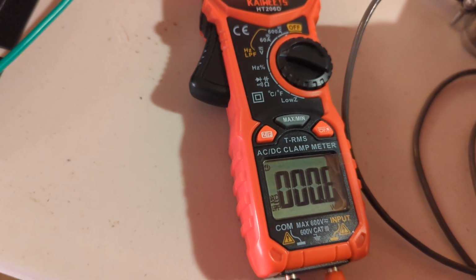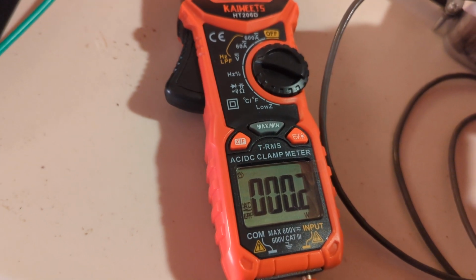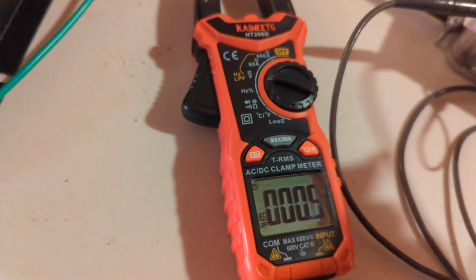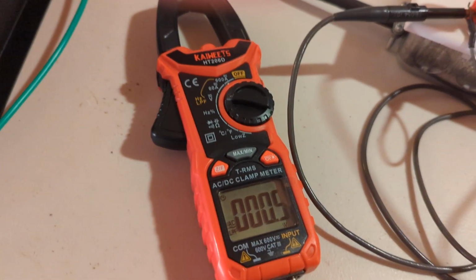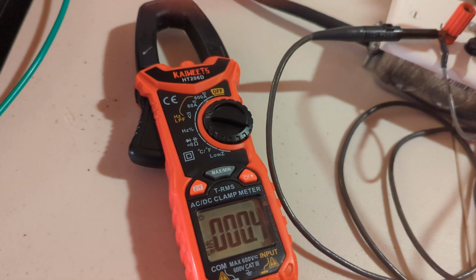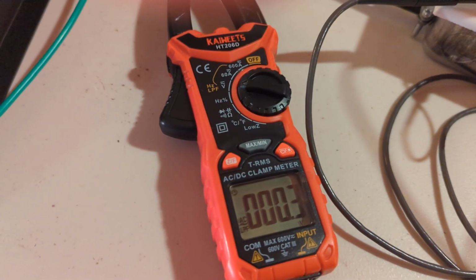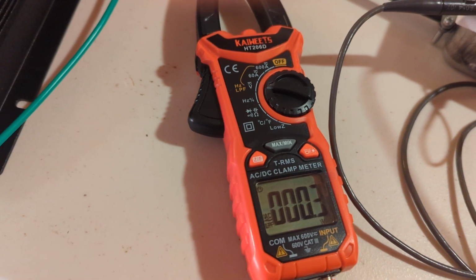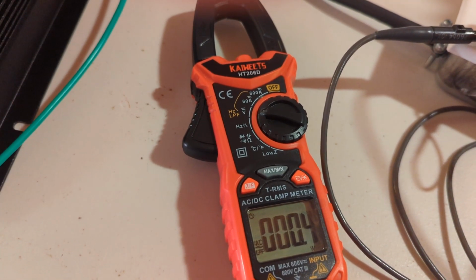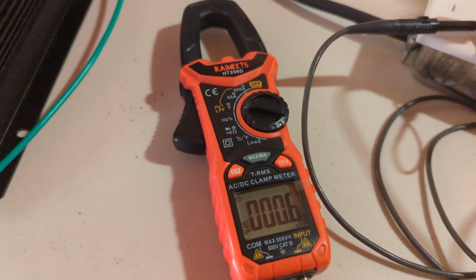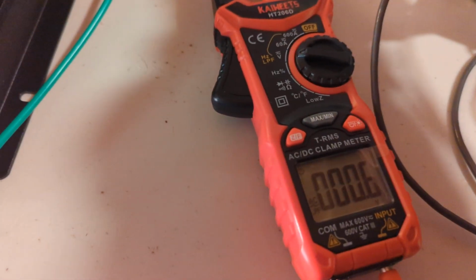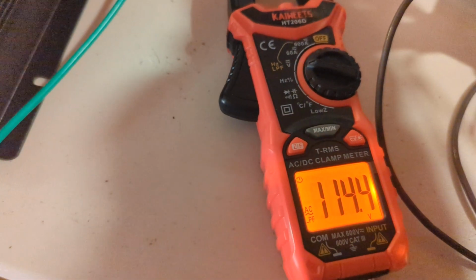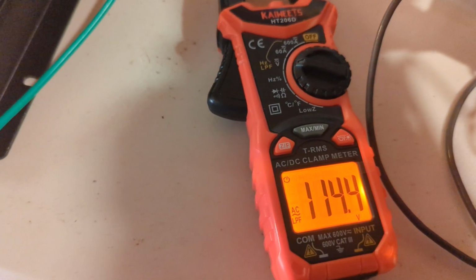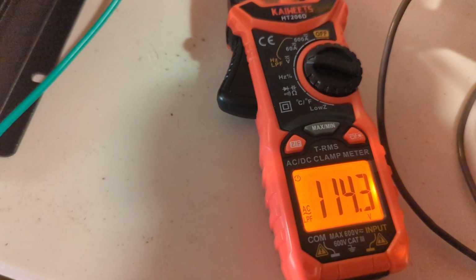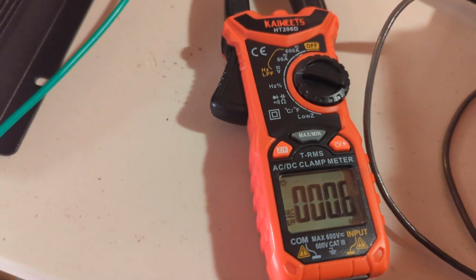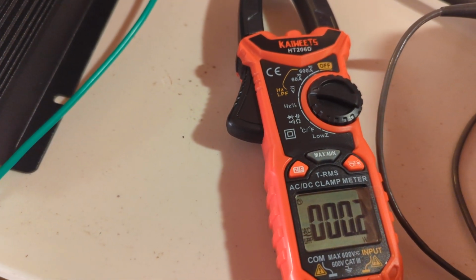So that's indicating to me this is not floating neutral. Much better than my other inverter, which was floating neutral, meaning voltage was carried on both the hot and neutral sides. That means for an AC circuit, if you flip off the switch, there's still power on the other side. So if you're screwing in a light bulb or plugging something in and touch the connector, you can still get burned, because a typical AC circuit only disables the hot side, expecting only the hot side to be carrying voltage. But with floating neutral, there's actually voltage on the neutral side.